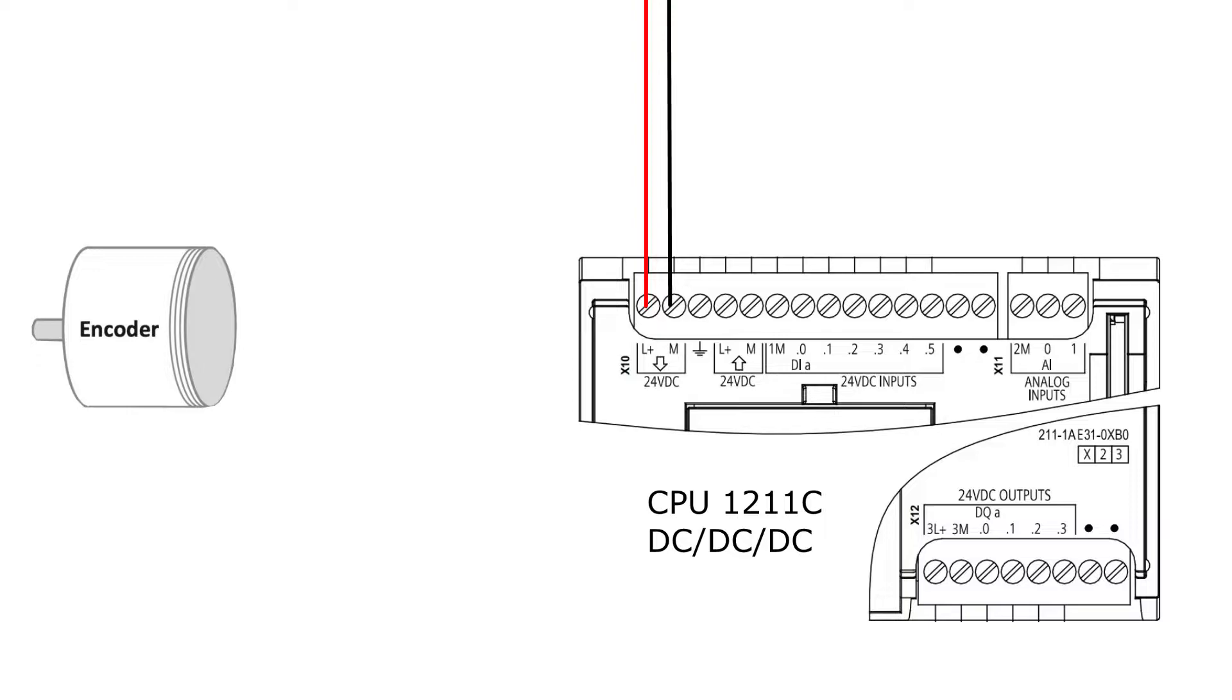The encoder I am using is an NPN encoder. This means it sends out 0-volt signals from the phases. So in my case, I will have to connect the 24-volt DC to my 1M terminal.